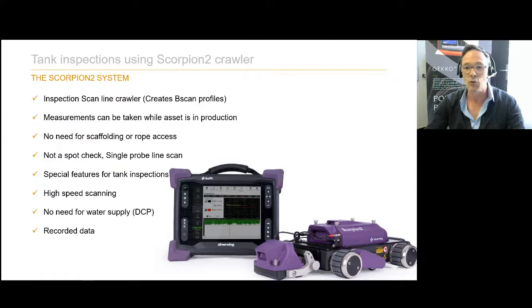The magnetic wheels on the Scorpion will actually allow the Scorpion to climb and make the measurement as it drives. So it's not a spot check. It creates a complete scan line over that whole tank. So a big advantage there, and I'll show you in later slides why that is. Also, this crawler is designed to measure at quite high speeds of 180 millimeters per second, allowing you to do tank shell scan lines very rapidly.